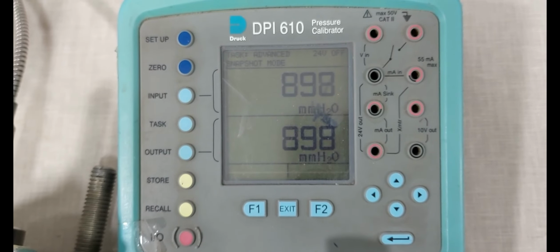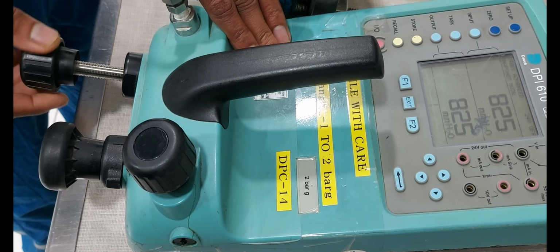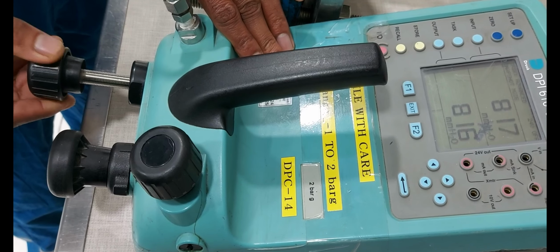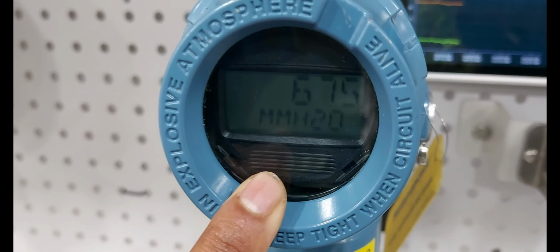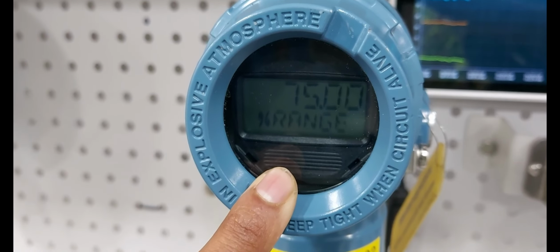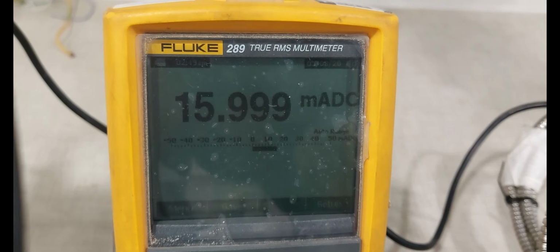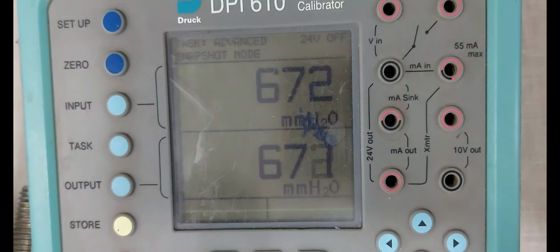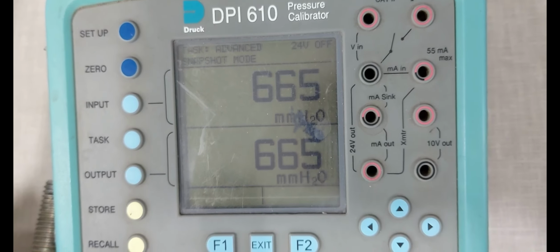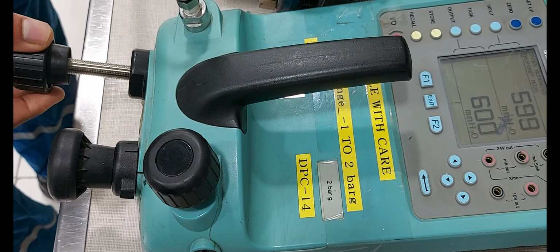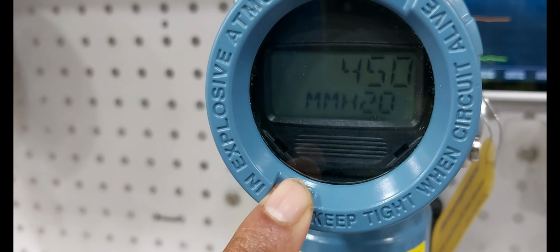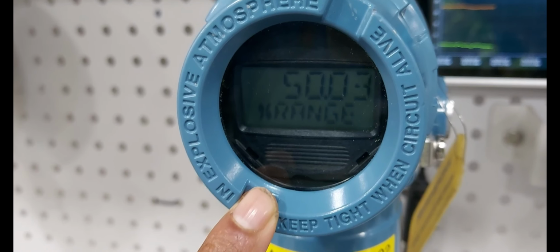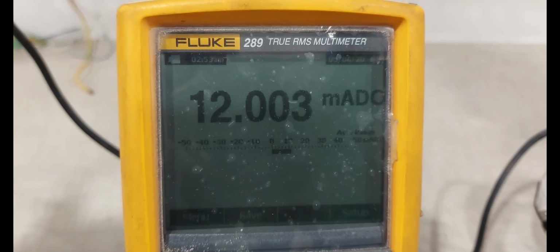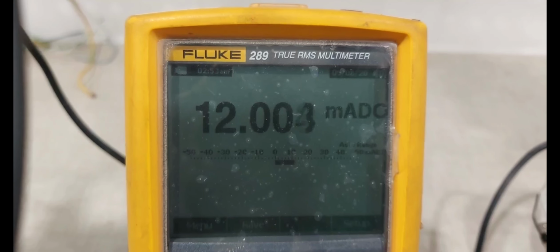Next we are checking the down-arrow falling condition. We are releasing the pressure slowly. Now falling value, 675 almost reached. Transmitter display showing 675 mmH2O, 75% also reached. Now output also showing 15.999. Next we are moving into the 450 mmH2O. Now 450 almost reached. Transmitter display showing 450 mmH2O, percentage 50.03%. Now output is showing 12.003 milliamps.